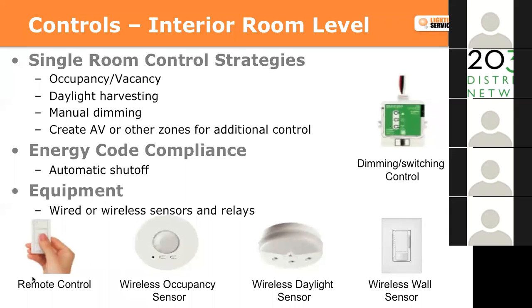You'll see that bullet point about creating what we'd call an AV row in a classroom. So if you have 12 fixtures in a classroom, 3 of them over the smart board - right now there's only one way to turn lights on and off. You can break apart each fixture, each row of lights, or just the row over the board, and turn it on and off or add dimming capability, even with just a 120 or 277 volt circuit in the room. So it adds a lot of functionality to the space.